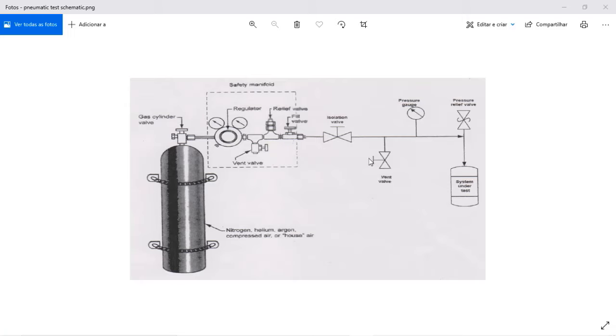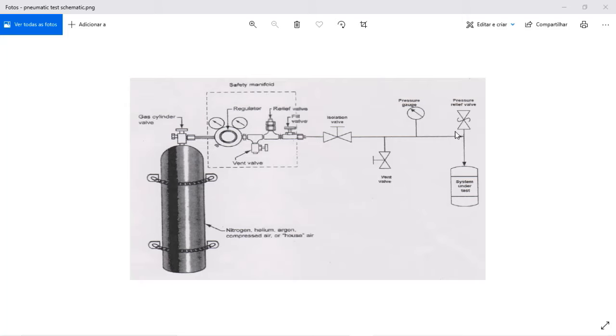You have the vent valve to depressurize the system in a controlled manner after you finish the pressure testing, and you always need to have a pressure gauge on site the whole time of the pressure test. Here in this schematic we have also another pressure relief valve and the system under pressure.